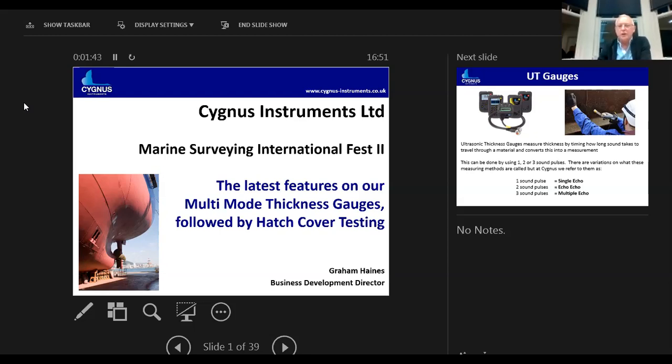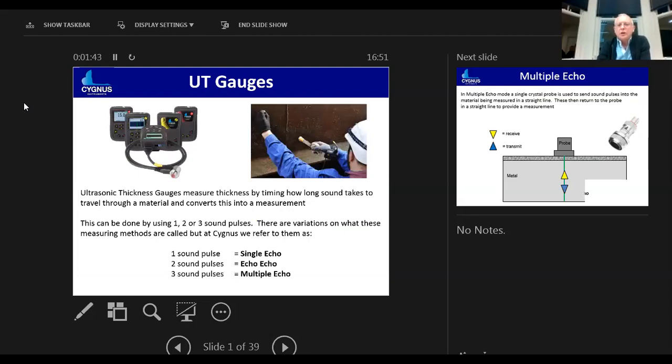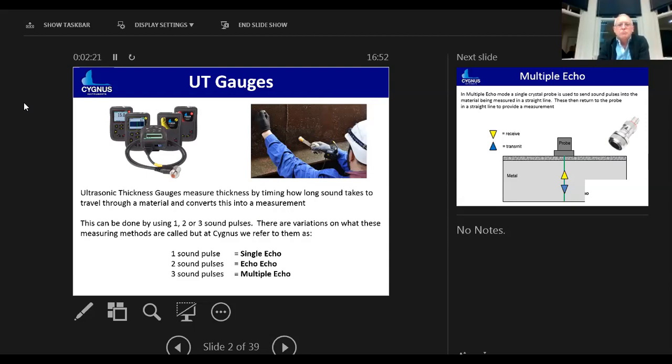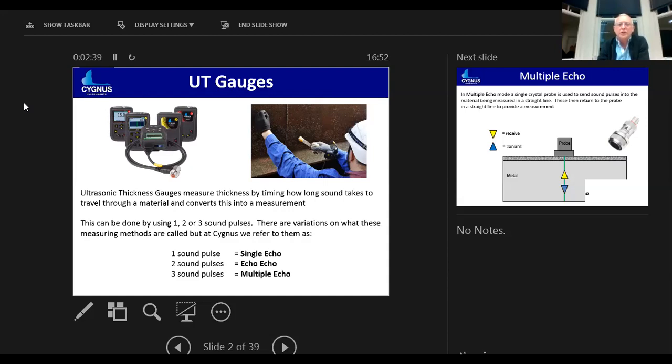I imagine the majority of you have a fairly good idea of what an ultrasonic thickness gauge does. We're primarily wanting to measure the thickness of steel from one side and if we can do it without removing protective coatings so much the better. Back in the early 1980s Cygnus developed a digital technique using multiple echoes for ultrasonic thickness gauges. This was quite revolutionary and it meant you didn't need to use flaw detectors where you had to back off the first and second echoes so you could ignore coatings and it was engineered into a digital handheld device.